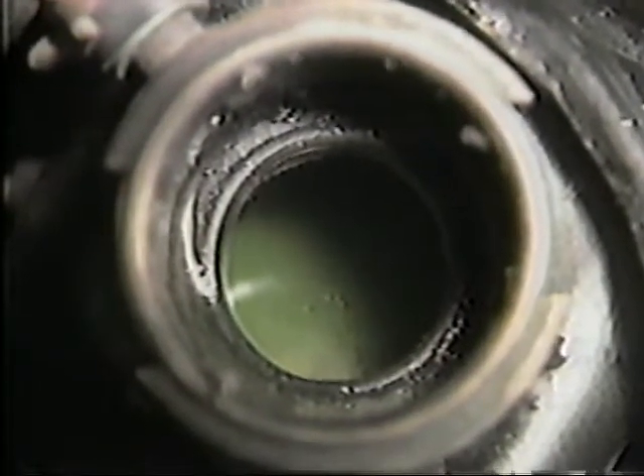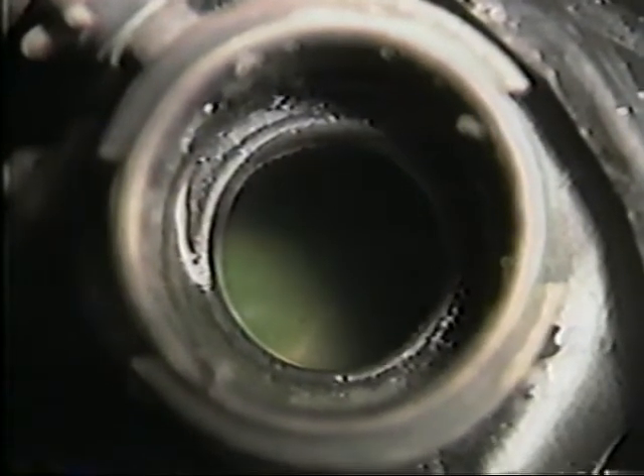Low coolant alarm and shutdown is somewhat different. As coolant leaks from the system, the ground at the coolant level probe goes away and the voltage within the coolant level circuit begins to climb. When the voltage at module terminal 6 reaches 3.5, the low water warning switch closes, connecting terminal 4 to terminal 5. Terminal 5 is connected to the light and bell, so voltage reaches them and a low coolant alarm is given. This situation will continue for about 30 seconds. If voltage remains above 3.5 for 30 seconds, the module will open the run switch and shut the engine down.